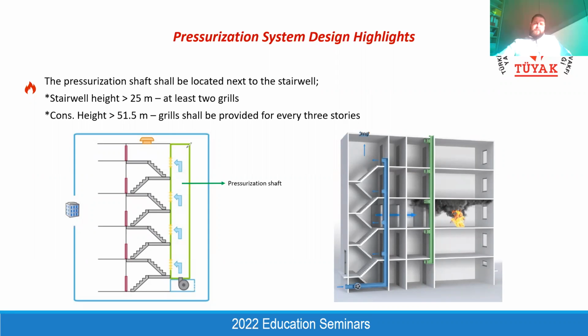You see here we have a shaft neighboring the staircase, and we have grills into the staircase for the pressurization air. Just for your information, the pressurization shaft cannot be separated from the staircase. It means the pressurization shaft shall be located just next to the staircase, because it is considered a part of the staircase. For example, we have a pressurization shaft here, we have a stairwell. Sometimes they try to link them with a hard duct system, a canal. It is not allowed, just for your information. When you have a staircase which needs to be pressurized, this pressurization shaft shall be neighboring the staircase.